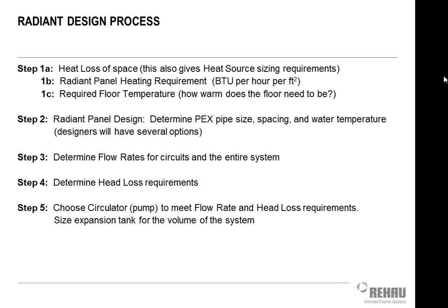All right, a couple of quick things on radiant design systems. Basically, the way you design a system is the same way you design any other hydronic system, or any system for that matter. The first thing is obviously doing a heat loss for the space. So, what's my load going to be? Whether it's a heating or cooling system, I'd be doing the same thing, and then working backwards from the space all the way back to the boiler, right? So what's my heat loss going to be?